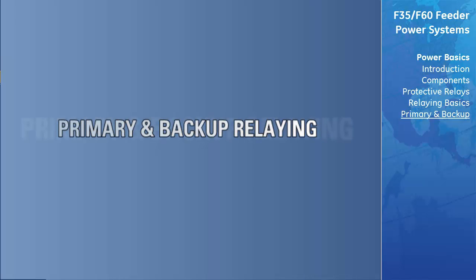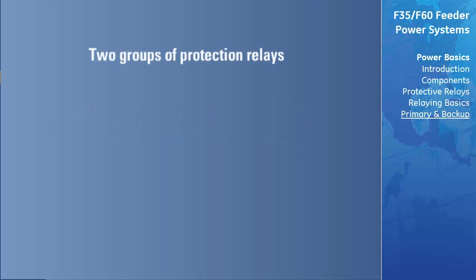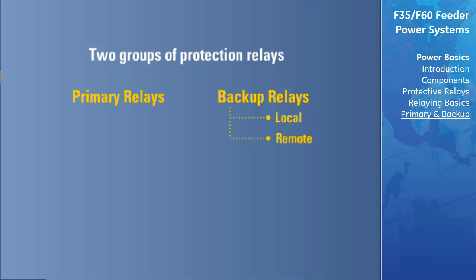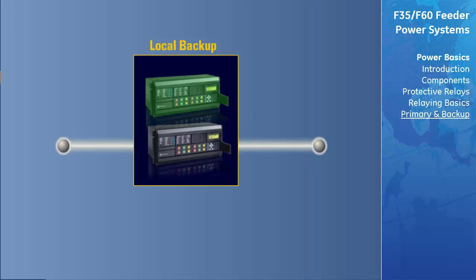In general, the most common faults that occur on a power system are short circuits. Relays dedicated to protection against short circuits fall into two groups. The first group are called primary relays and are the first line of defense, while the second are called backup relays and function only when primary relaying fails. Backup relaying can be classified as either local or remote. Faster reacting backup relaying can be achieved by using local backup relaying systems, meaning the relay providing backup is located on the same component being protected by the primary relay.